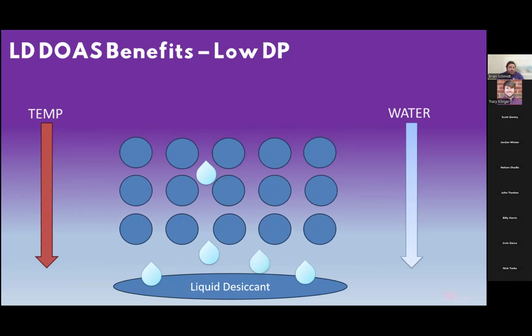And if we mix the two, if we continue to drive that temperature very, very low and add in liquid desiccant, now is when we can really start wringing a lot of moisture out of the environment. Now is when we can start getting it to much lower dew points. So again, we don't need necessarily as low of temperature to get to normal supply air dew points, but to get to very low dew points, obviously we're going to have to drive the temperature down farther.